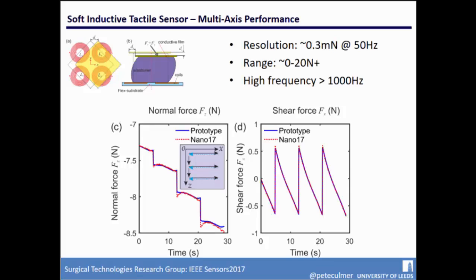One of the inherent limitations built into this is the physical hysteresis effects that come from the elastomer. To some extent, you can see that as a design problem that you can tune for your particular application. If you need a high dynamic response, then you'd have to use something that was stiffer and that bounced back more quickly. So compared to something like the ATI sensor, it does suffer in that respect. But using this chip and this setup, we can sample up to about 1 kilohertz, and we're looking at force ranges of 0 to 20, 0 to 30 newtons, something like that. And the resolution that we're getting is about 0.3 millinewtons, or slightly below, when you operate at 50 hertz. I should say that the measurement precision varies with the sampling frequency to some extent, because there's some smoothing that goes on in the inductance measurements.